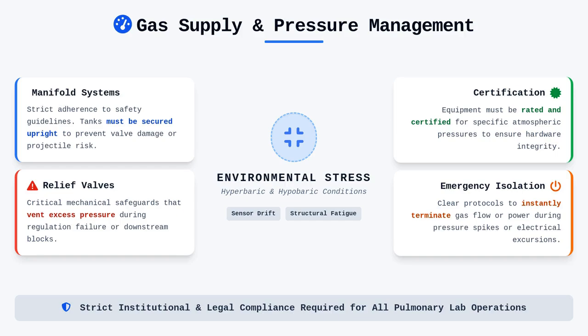Managing gas supplies and pressure relief variables requires strict adherence to institutional and legal safety guidelines. Every pulmonary lab relies on a manifold system to deliver calibration gases, and these tanks must be secured upright at all times to prevent valve damage or accidental projectile displacement. Pressure relief valves serve as critical mechanical safeguards within these gas delivery circuits, acting to vent excess pressure should the regulation system fail or an obstruction occur downstream. When dealing with environmental variables, specifically in scenarios that approach hyperbaric or hypobaric conditions, the mechanical stress on the hardware increases exponentially. You need to ensure that the equipment is rated and certified for the specific atmospheric pressures it will encounter. Otherwise, the internal sensors may drift, or the hardware enclosures might suffer structural fatigue. Establishing clear protocols for hardware emergency isolation allows you to instantly terminate gas flow or power if a sudden pressure spike or electrical excursion occurs.